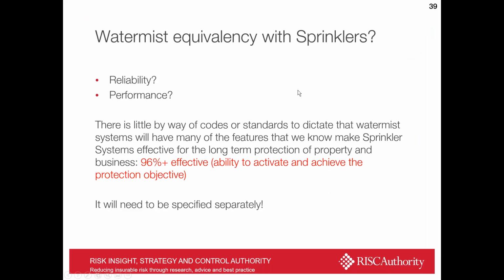So, sorry, in that slight whirlwind, I hope it wasn't too confusing, look at what makes reliability. Currently there's little by way of codes or standards to dictate that water mist systems will have many of the features that we know make sprinkler systems effective for the long-term protection of property and business. I have seen justifications of water mist systems which have basically said that sprinkler systems have a tank, a pump, lots of pipe work and the nozzles, and they're 96% effective. Our water mist system essentially is made up of a tank, a pump, some pipe work and some nozzles, so we can infer the same level of reliability. Totally wrong, but I do see it written down occasionally.